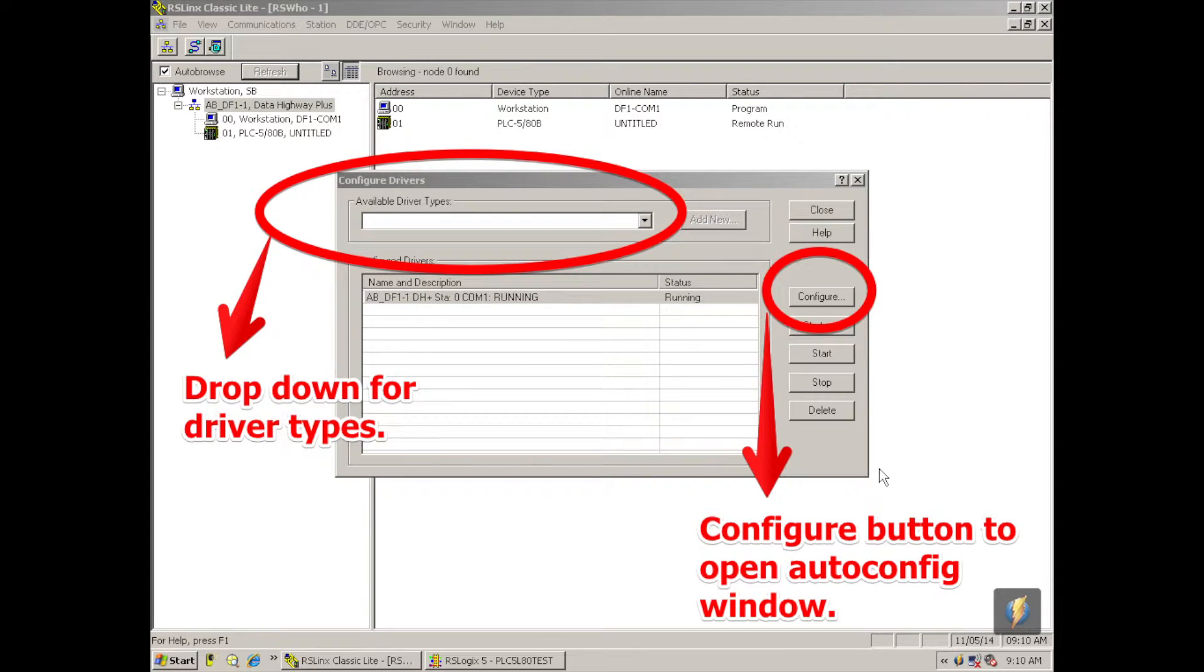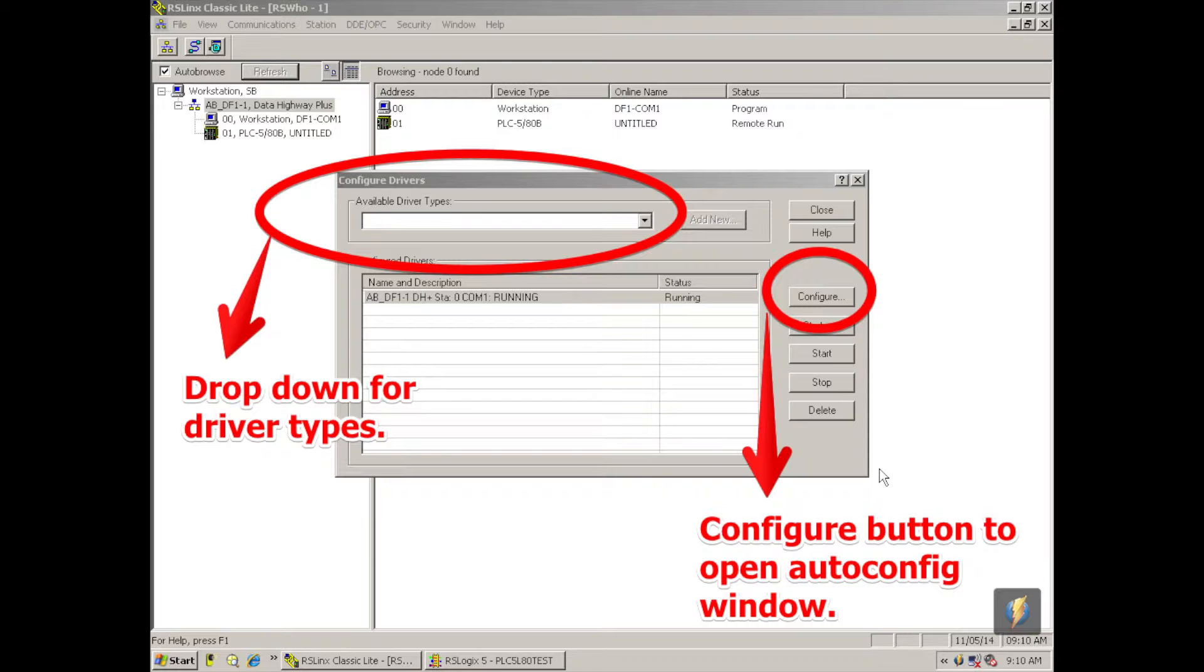Now in order to link up to it, I'm going to hit the configure drivers icon, which is that squiggly line with the two computer leads at each end. I'm going to click that. And the available driver types, well this is the RS-232. So if I hit the drop down menu, if I don't already have a driver configured, I'm going to select the RS-232 DF1 devices.